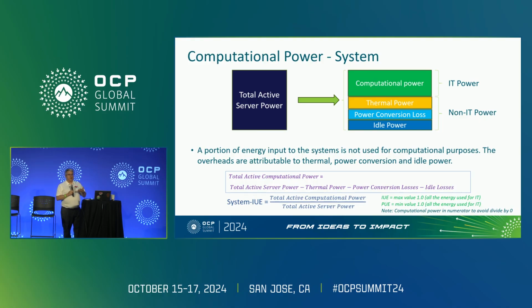It turns out that when you have GPUs consuming kilowatts of power, if all their power sources run through DC-DC converters at 80% efficiency instead of 95%, times 1,000 watts, that suddenly becomes a loss of 150 watts of waste heat in that conversion. So that's an area we really need to look at.